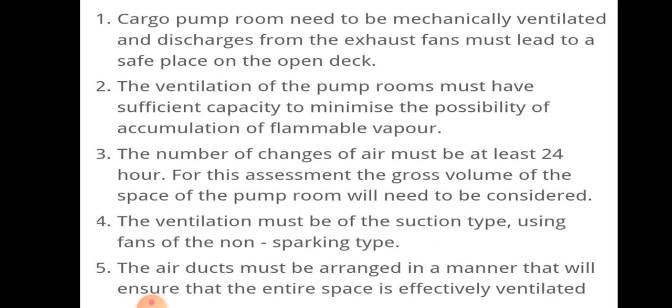In summary: cargo pump rooms must be mechanically ventilated with exhaust leading to a safe place on the open deck. Ventilation must have sufficient capacity to minimize accumulation of flammable vapour, with at least 24 air changes per hour based on gross volume. Ventilation must be suction type using non-sparking fans, with air ducts arranged to ensure the entire space is effectively ventilated.